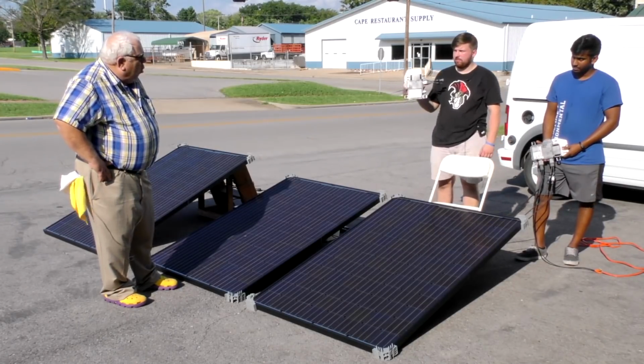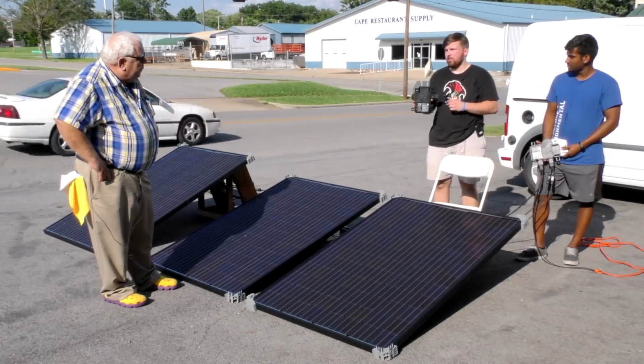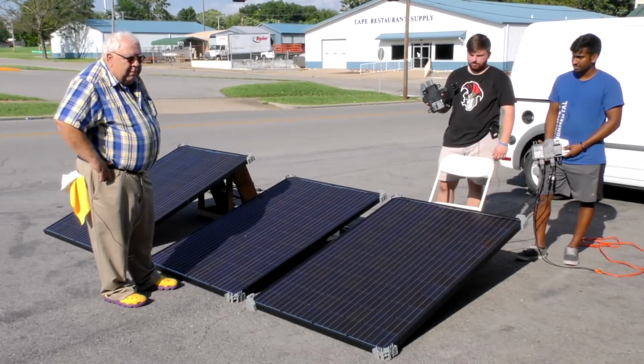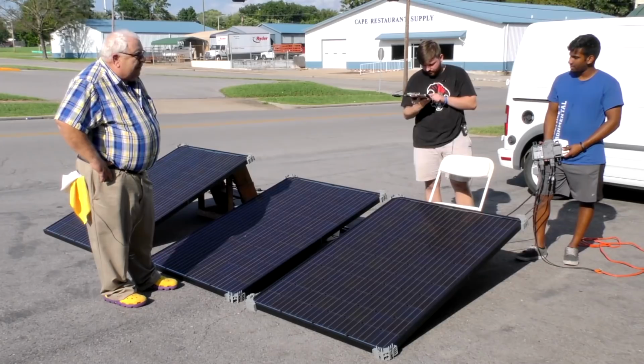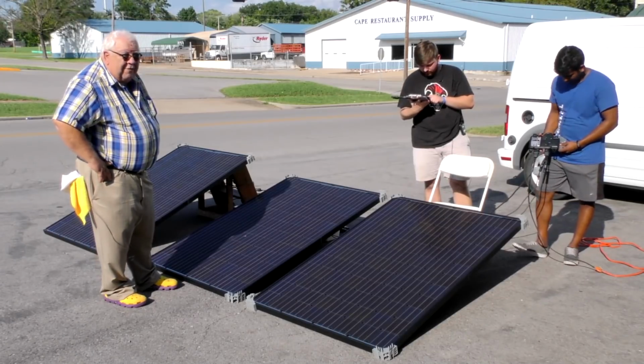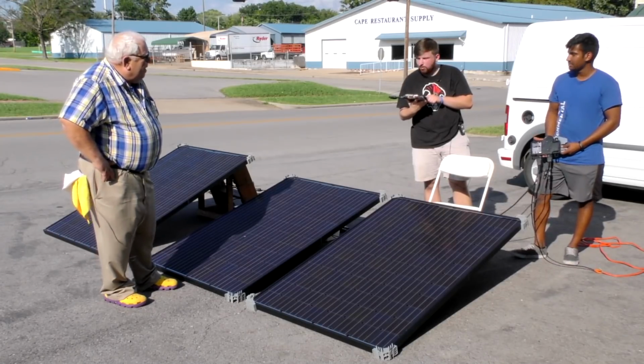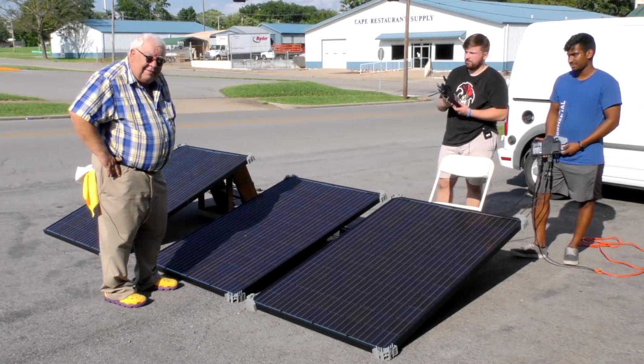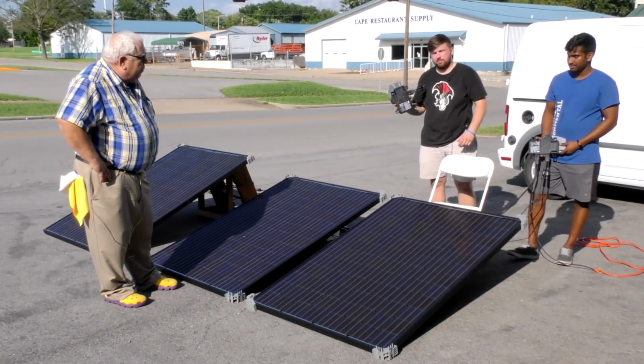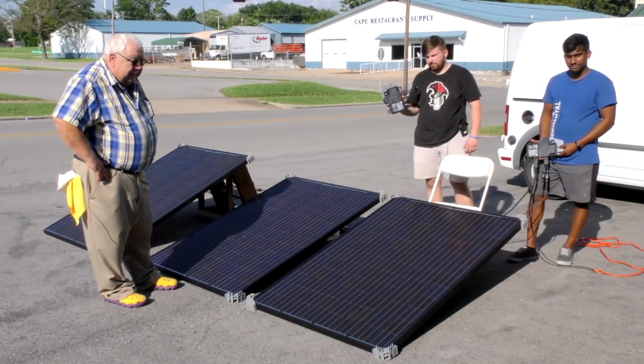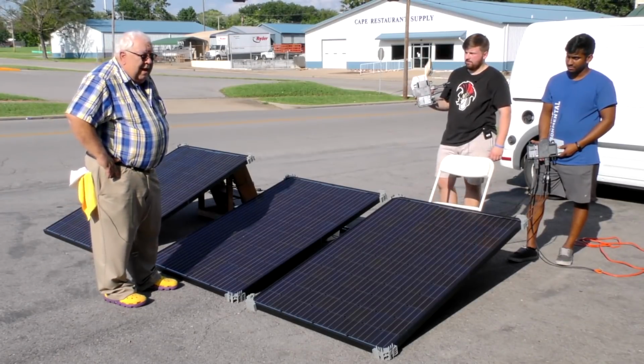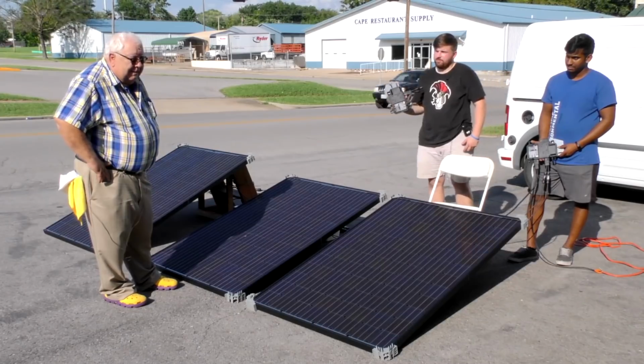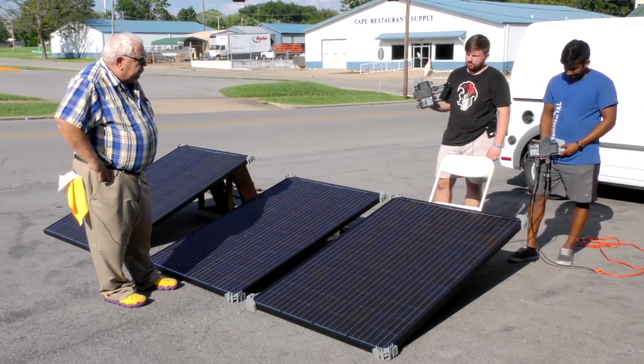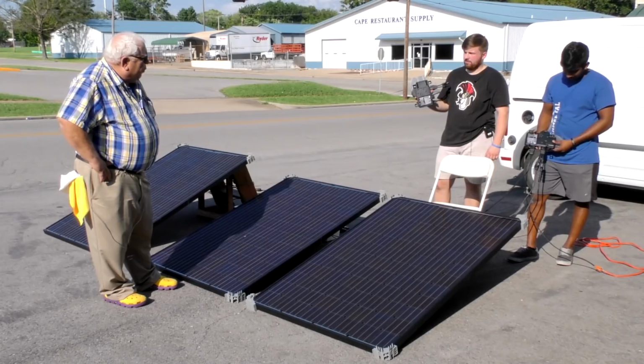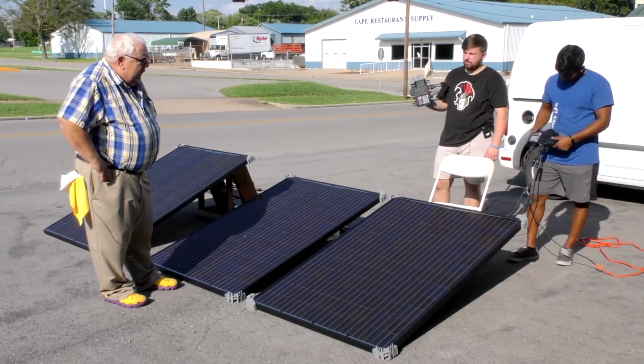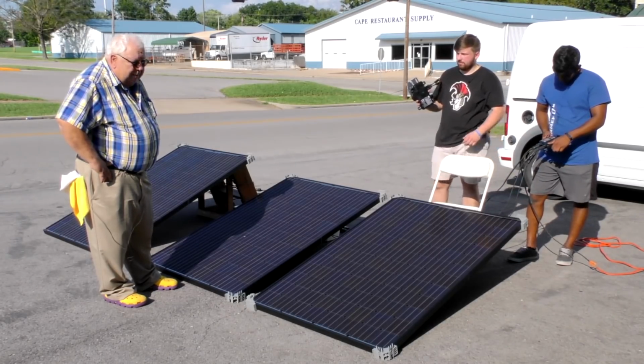What's the open circuit voltage of the panel? 70.5. And what's our range of DC input on the Enphase IQ7x? 25 to 79.5. There you go. That's the magic. These have been developed by Enphase in cooperation with Panasonic, specifically as ostensibly the first 96 cell microinverter. These are good for about 300 or 350 watts, and these panels are about 325.